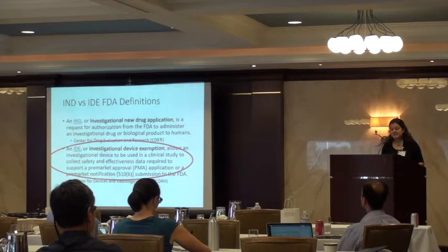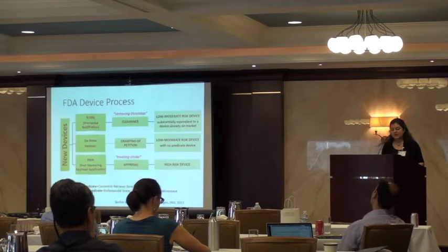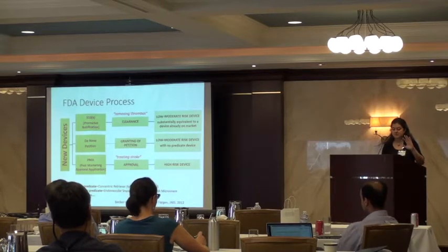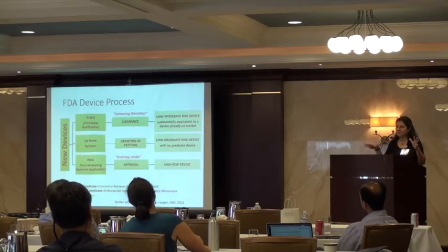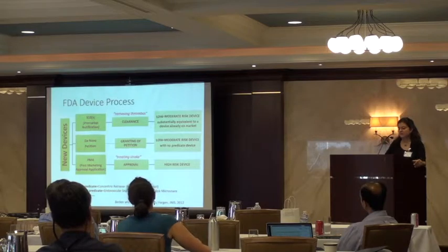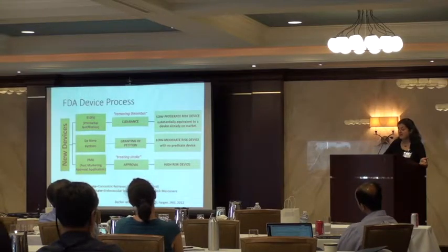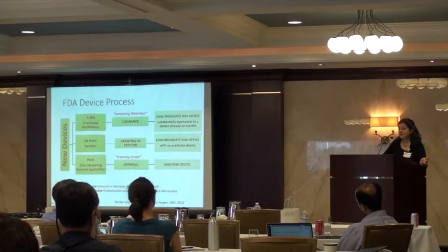So moving on to IDEs, I think the framework is very different there. We're talking about a framework towards getting FDA clearance or approval for a device, and it has its own kind of lingo around it for those who aren't familiar. There's the 510K clearance pathway, and that's for low or moderate risk devices. A device can qualify for that if it's substantially equivalent to a device already on the market.